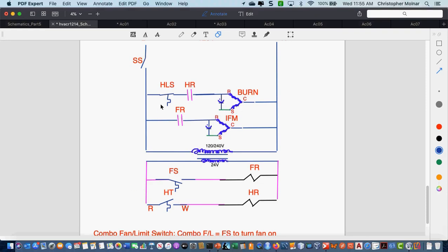Okay? Now, boilers. When we start talking about boilers later on this term, boilers use the high limit switch. It's an operating control as well as a safety. Remember I told you there's several different types of controls. Boilers use high limits as an operating control as well as a safety. Boilers, we set the high limit switch to about 190 degrees. I don't want the water to boil. I want it to be hot. So the burner actually comes on and off, on and off, on and off based on a limit switch. In forced air equipment, the limit switch is a safety.